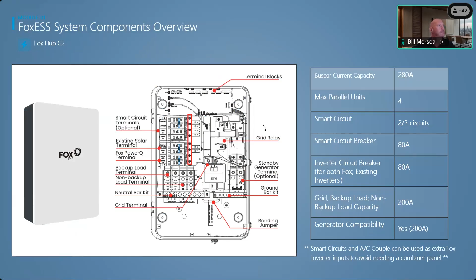So there are options that we can do with either hub or non-hub systems. So some people ask, well, do I have to have the hub? I will tell you that no, there are situations where you don't need a hub, but here's what I will tell you. If you're doing a whole home backup, you're absolutely going to have to have the hub. If you're doing a partial, right? Or maybe you're just doing a DC only, right? You won't need to have the hub for that, but those are very limited situations. Even in those situations, I would still recommend using the hub, because if you ever want to upgrade the system to a whole home backup, or if you ever want to add batteries, you're going to need that hub to be able to do that.